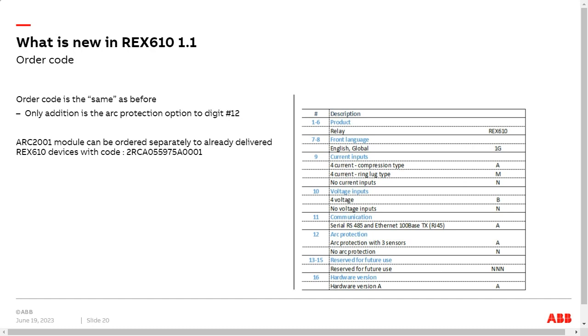So you can order, for example, one device with only CT installed, this ring lug type. And then if you like, you can order the ARC protection and the voltage module loose, and then you just add the voltage module to those devices that need that functionality, and so on. You can keep these modules on the shelf locally. So in total, there are 12 variants now. But if you only use ring lug and not compression type, then the variants are reduced to 8. And if you decide that you never order the ARC protection directly from the factory, you keep it loose, then it's reduced even further, so then it's only 4 variants. So this is how you can limit the number of variants on the shelf.